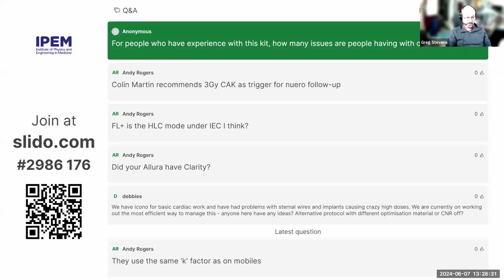We had major issues with it, mainly because our air handling units weren't running properly, and the detectors especially are really sensitive to changes in temperature, which caused all sorts of issues. All sorts of problems. We ended up almost having to recommission one of the units. So I can see problems later on as the system ages and your air handling units become slightly less efficient. It really does belt out an awful lot of heat. So that's one problem.